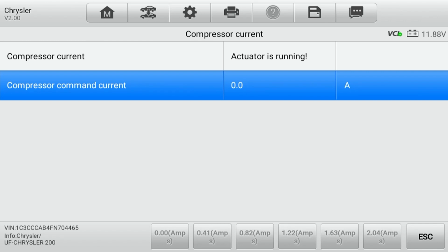Now I can go to 0.41 of an amp. It's telling me the compressor current is 0.41 and the compressor command current is 0.34. So they're close, but there's a little bit of a mismatch there, as you can see already.